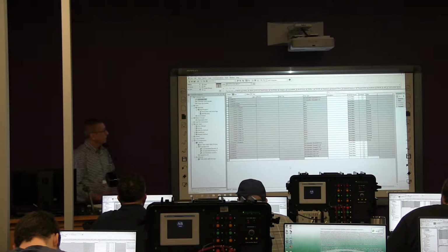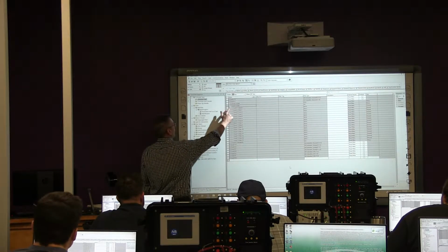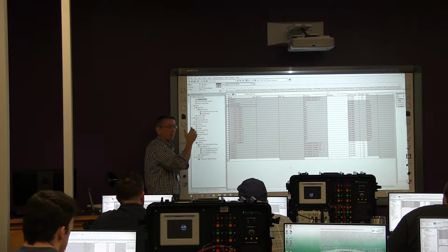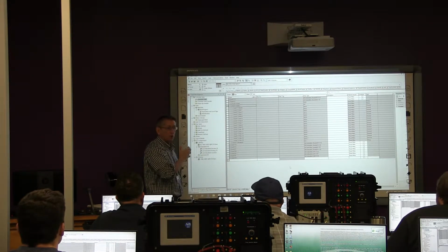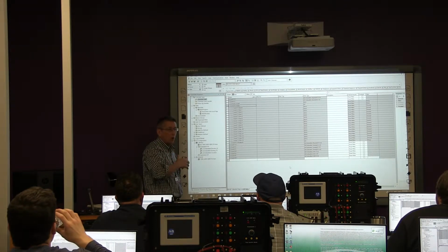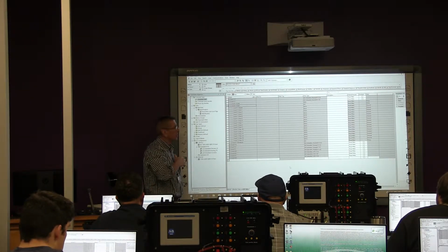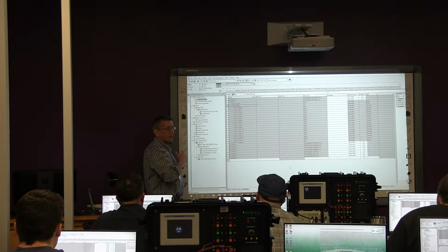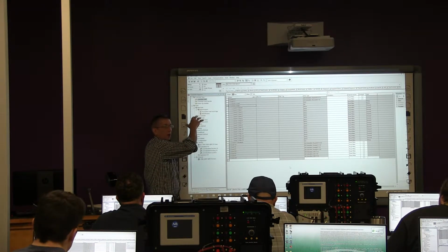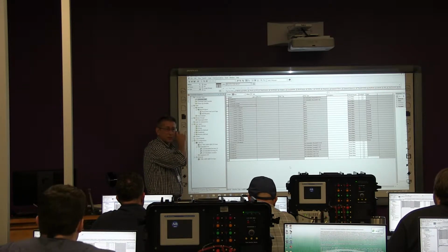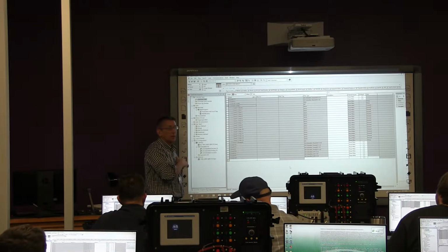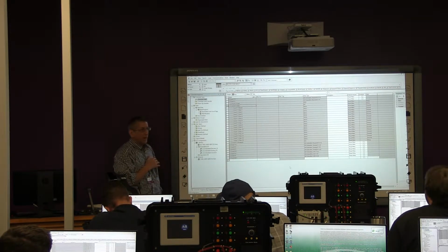You don't have to do this, but just look up here. So we have these controller tags that are already in there, right? All of the I/O are always what kind of tags? Inputs and outputs. All your I/O? Local. All of your inputs and outputs are always going to be controller tags. They're always going to be global tags, because we want any program to be able to access those tags, right? So they're always going to be global tags.